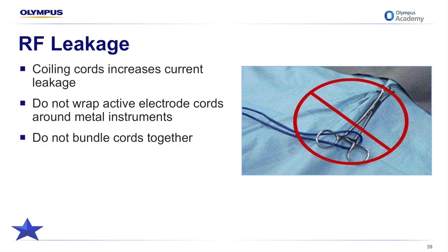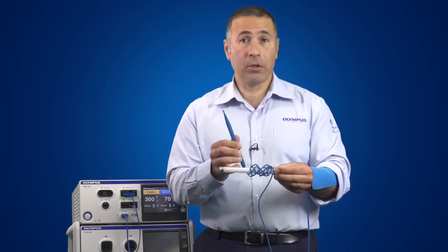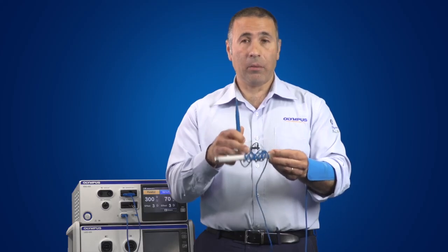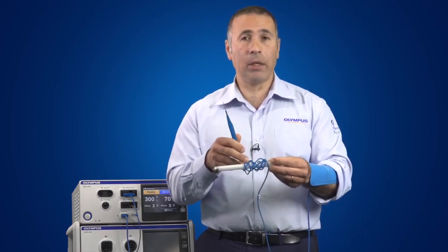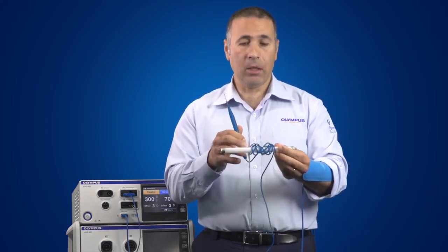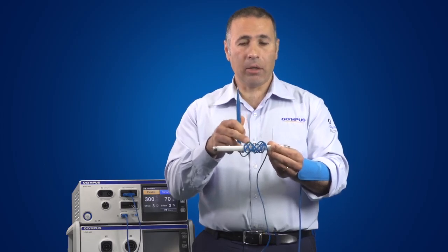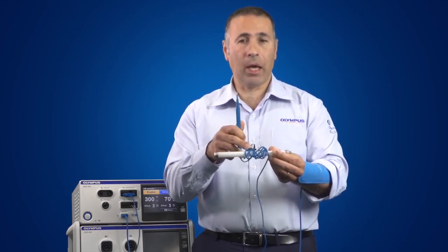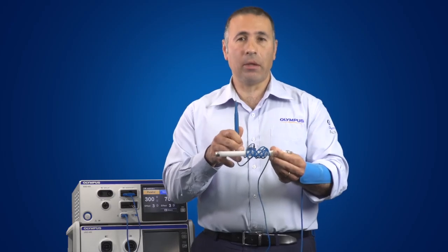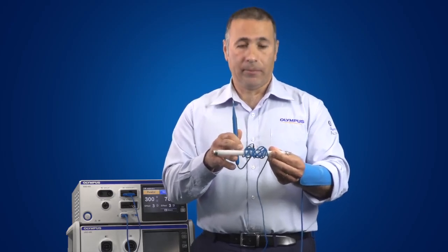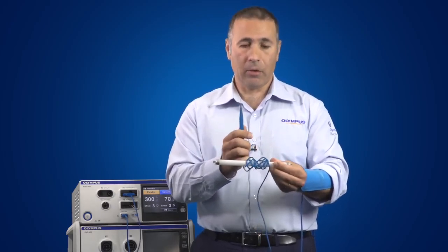I will now give you a demonstration regarding high frequency current leakage. So now I'm going to give you a demonstration to show why we shouldn't wrap and bundle cords together or wrap them around metal instruments. Because what's going to happen here is that the current that's leaking out of the insulation through the active electrode is going to excite the neon within this fluorescent globe to light it up. Here we go.